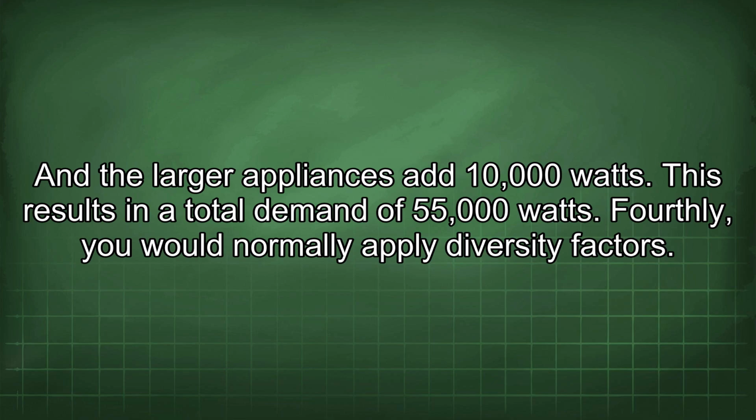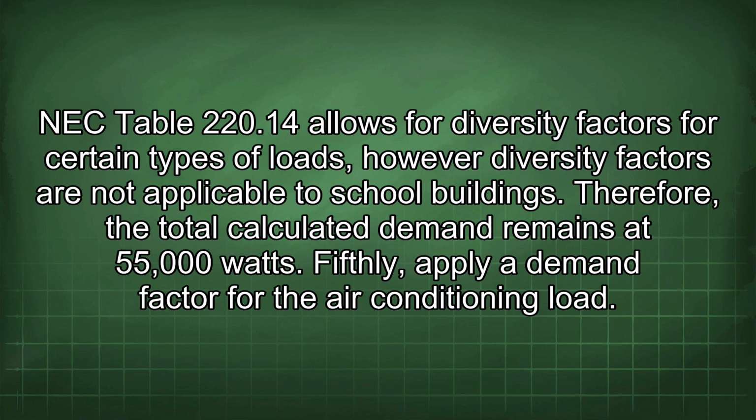Fourthly, you would normally apply diversity factors. NEC Table 220.14 allows for diversity factors for certain types of loads, however diversity factors are not applicable to school buildings. Therefore, the total calculated demand remains at 55,000 watts.